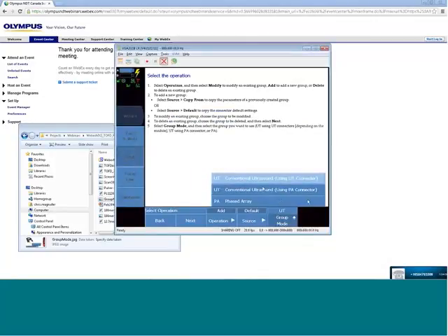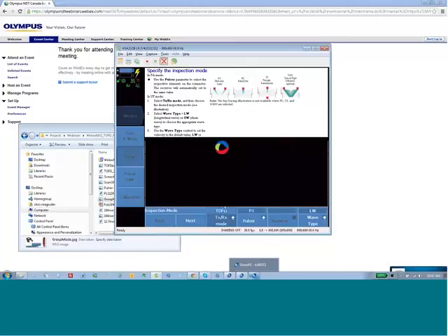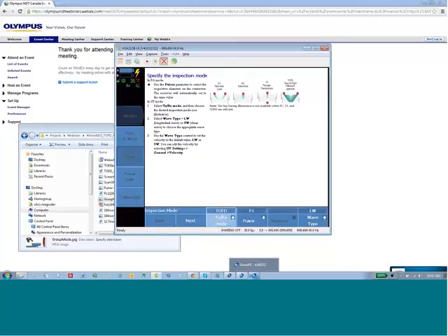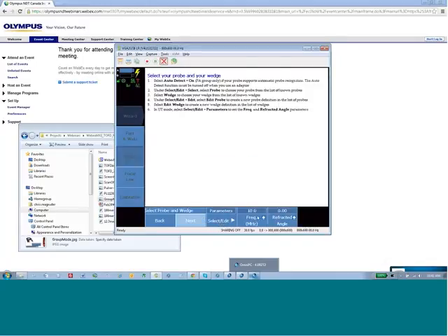So we're going to select conventional UT using the conventional UT connector and select next. Okay, change the mode to time of flight, and we have selected the P1R1 by default, so the pulser knows the instrument's LEMO connections. It's an L-wave inspection. Select next, 10 megahertz.